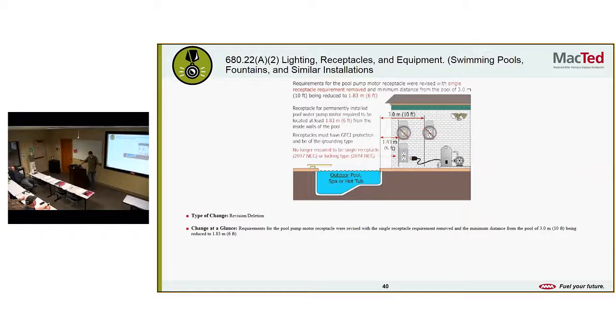Lighting, receptacles, and equipment, swimming pools, fountains, and other similar installations. Requirements for the pool pump motor receptacle were revised, with the single receptacle requirement removed and the minimum distance from the pool of 10 feet being reduced to 6 feet. So now, if you have a permanently installed pool water pump, the receptacle needs to be 6 feet from the inside walls of the pool. Receptacle must have GFI protection, and it can now be a duplex receptacle. Gives you a little bit more leeway there.